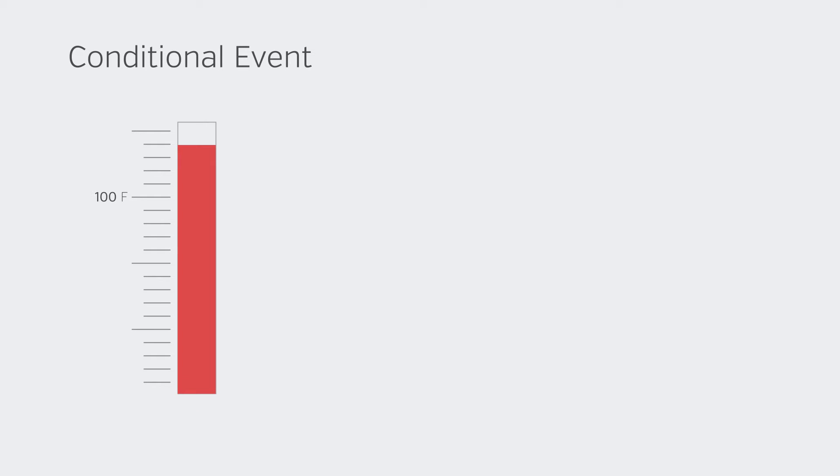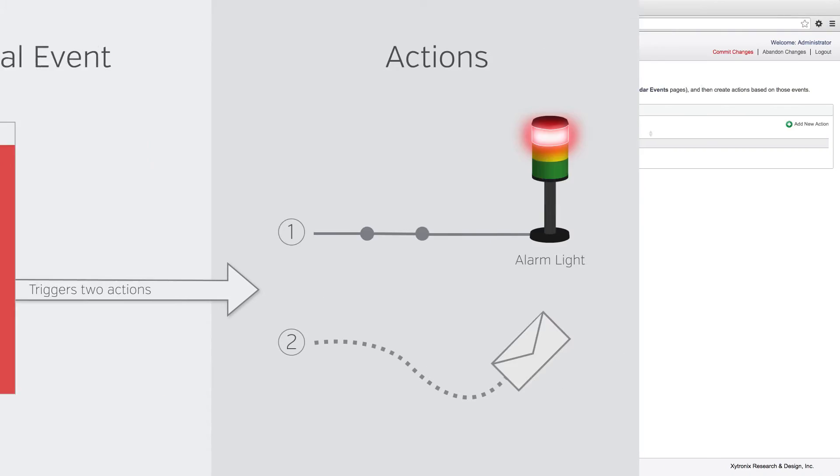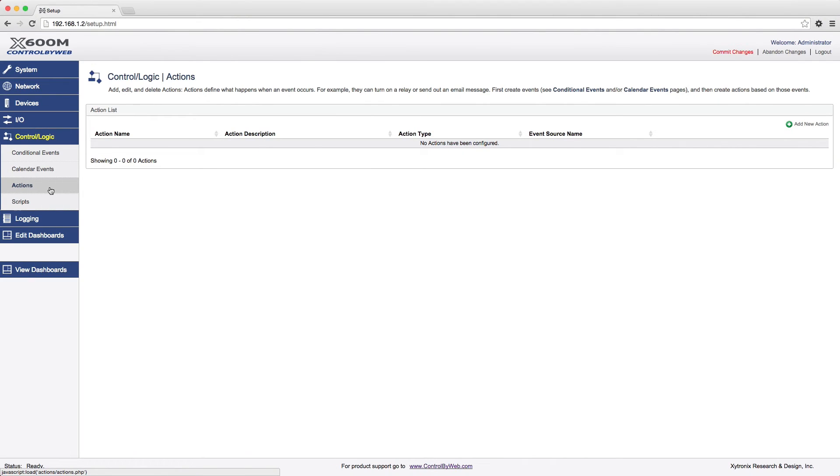For example, a conditional event can occur when a temperature sensor reads above 100 degrees Fahrenheit. This can then trigger two actions. One action turns a relay on, which illuminates an alarm light, and a second action sends an email alert. Because events and actions are configured separately, it allows for complex conditions and reporting that are often needed for many real-world applications. Remember to first set up events and then set up actions.